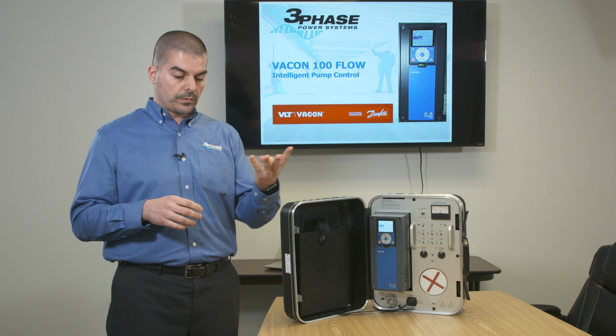And some of the things I want to list that are special about this drive is that we can mimic what the PID controller can do. Namely, when a pump starts, we want to be able to soft fill the pipes if we have our own PID controller inside the drive. We want to control the pressure of a pipe, we want to control flow, we might want to control temperature, so on and so forth.